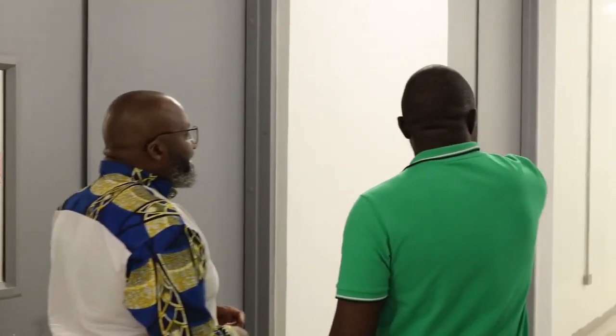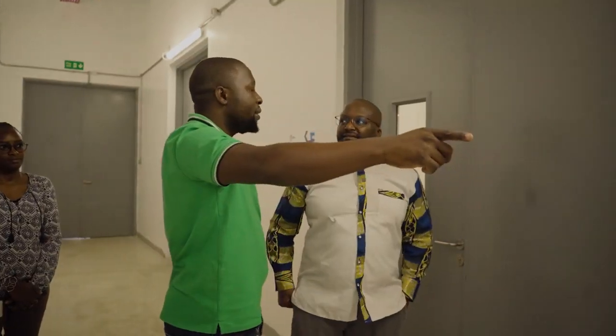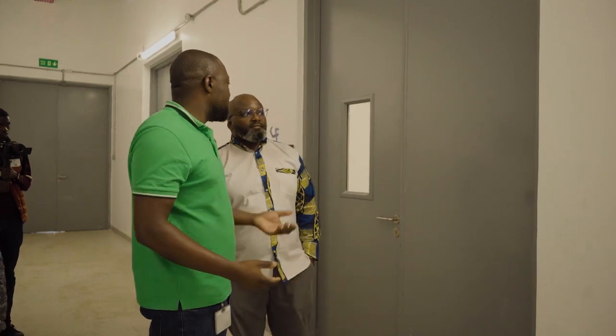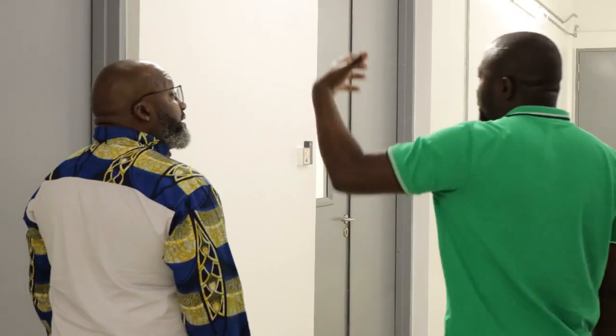We have a low voltage room. These are the low voltage rooms, with the low voltage distribution boards and the UPS. The UPS is our power backup device in case we lose power or have a blackout from KPLC, to sustain our IT equipment. It's sized for a minimum of 9.5 seconds to sustain the load before the generator kicks in.